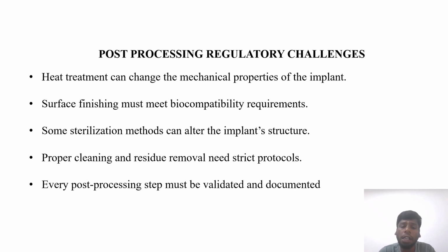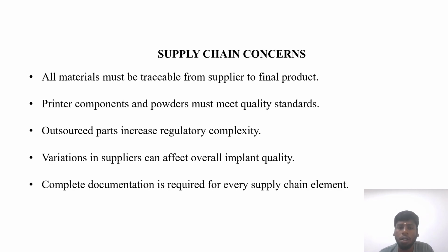So proper cleaning and residue removal need a strict protocol. Proper cleaning should be done, and residue should be removed. If there is any dirt inside the 3D implants, we should use strict protocols to remove it. So every post-processing step must be validated and documented. What steps are performed in post-processing should be validated and documented for further purposes.